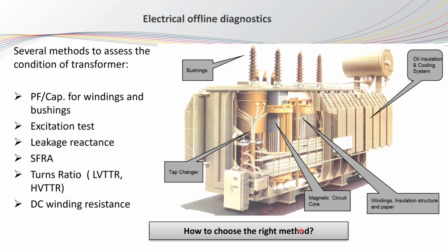When it comes to the electrical offline data, there are several tests that can be done when the transformer is de-energized, like power factor and capacitance, excitation test, leakage reactance, SFRA, turns ratio, and DC winding resistance. Each one of them has its own purpose in order to do the diagnosis of the transformer.